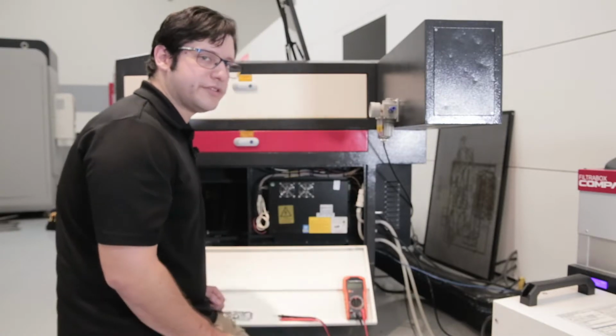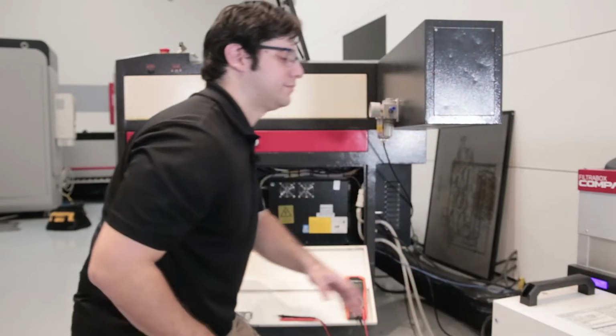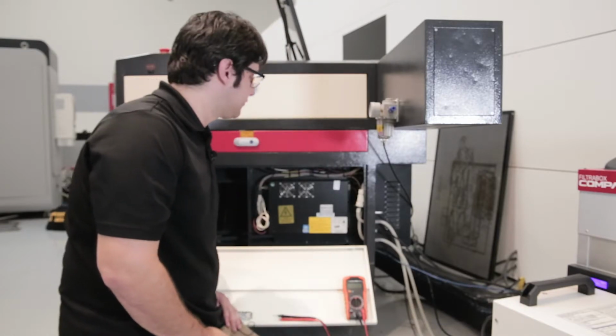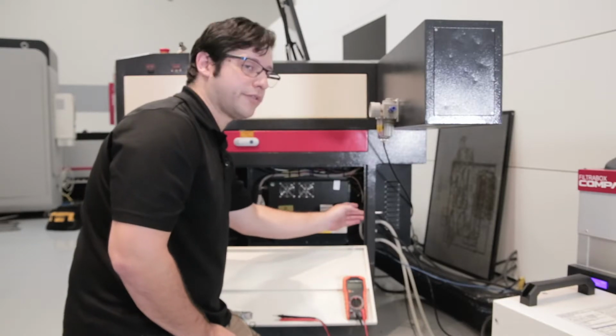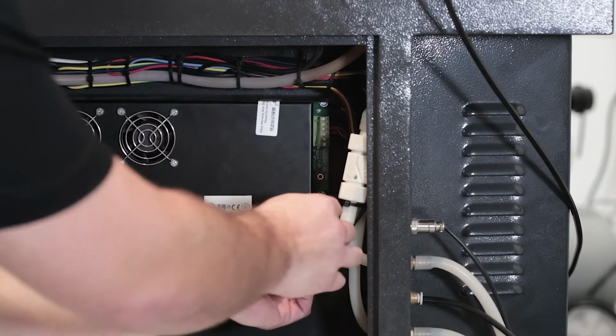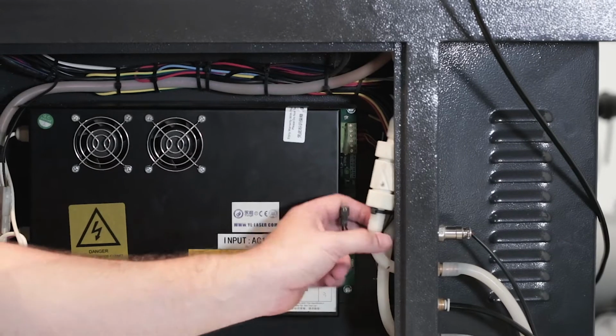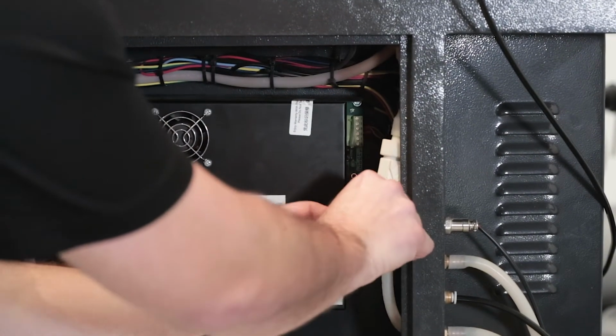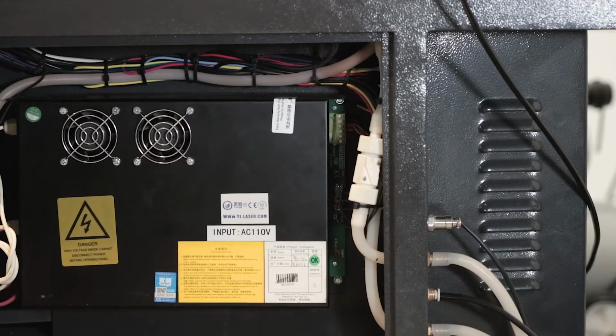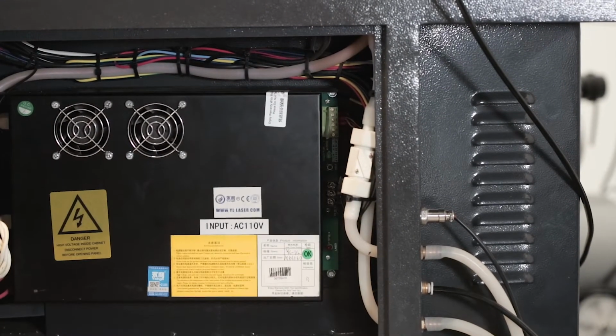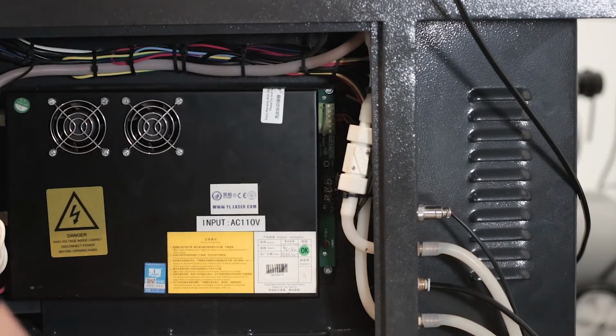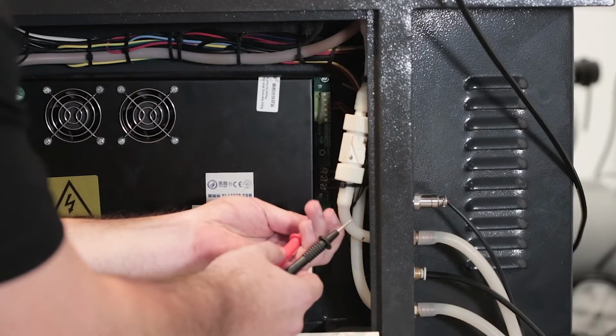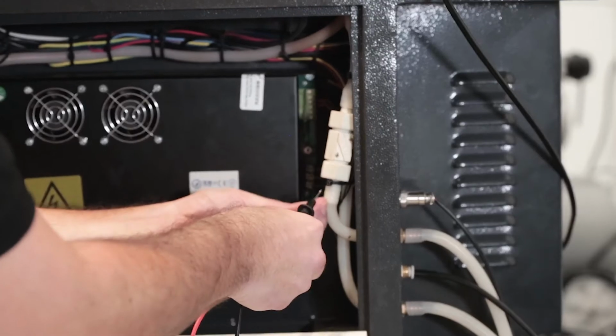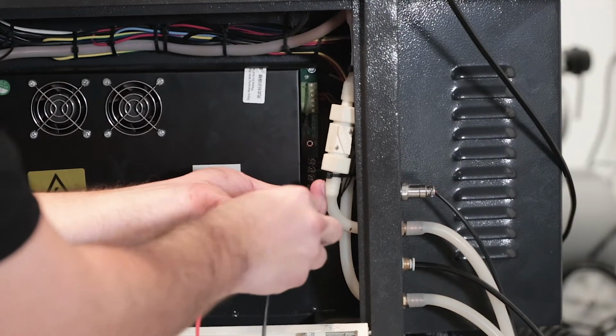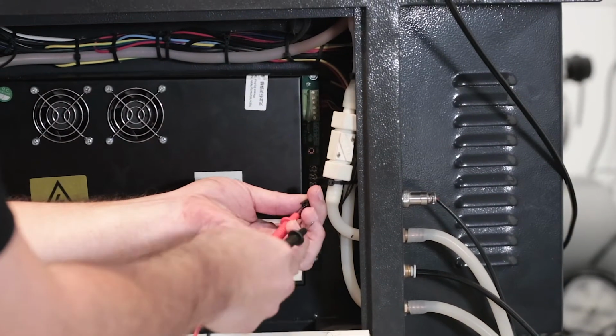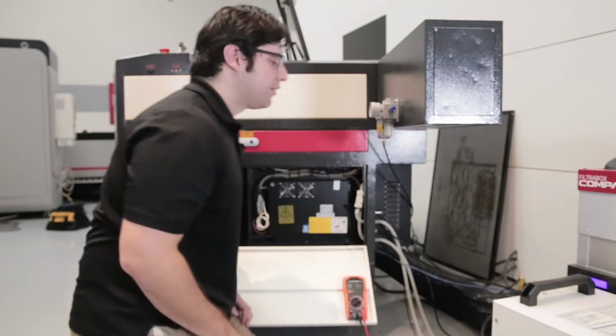Now you're going to make sure that your chiller is on when you check it. Your connection, just like on the door interlock here, it's a quick disconnect. You can go ahead and take that apart. Now since water is flowing through it, the float should be triggered. So we're going to go ahead and check continuity on this float and make sure that it does have that. So it does have continuity on it.